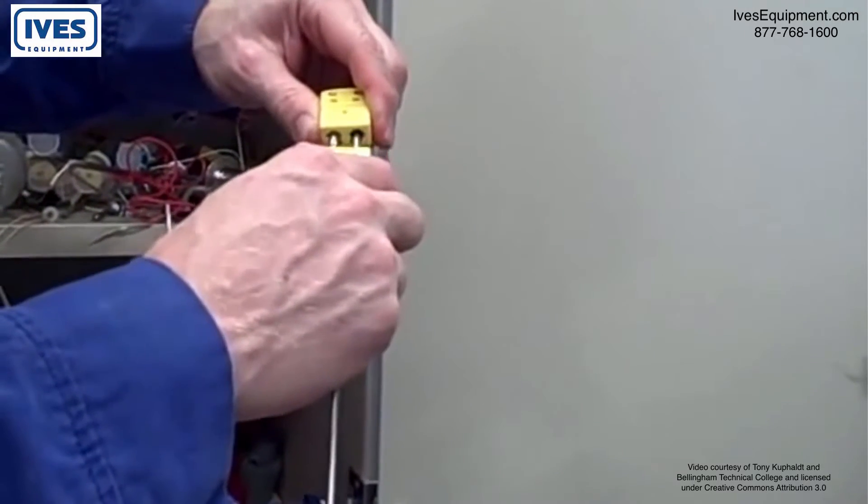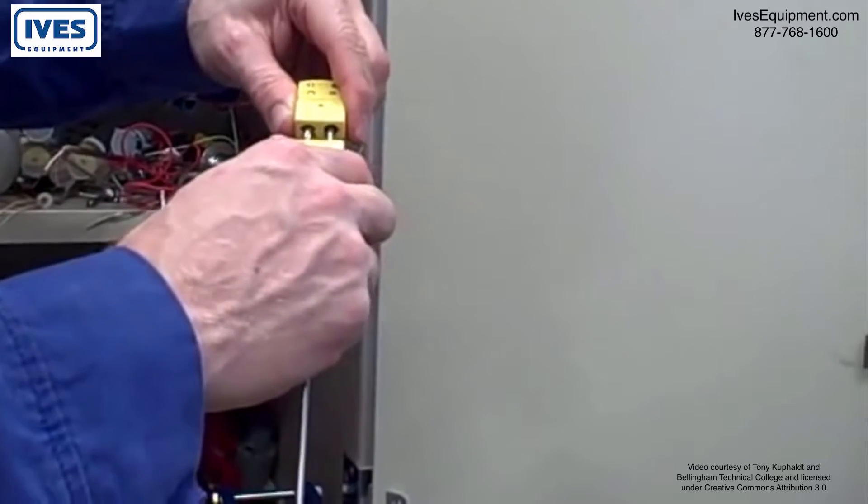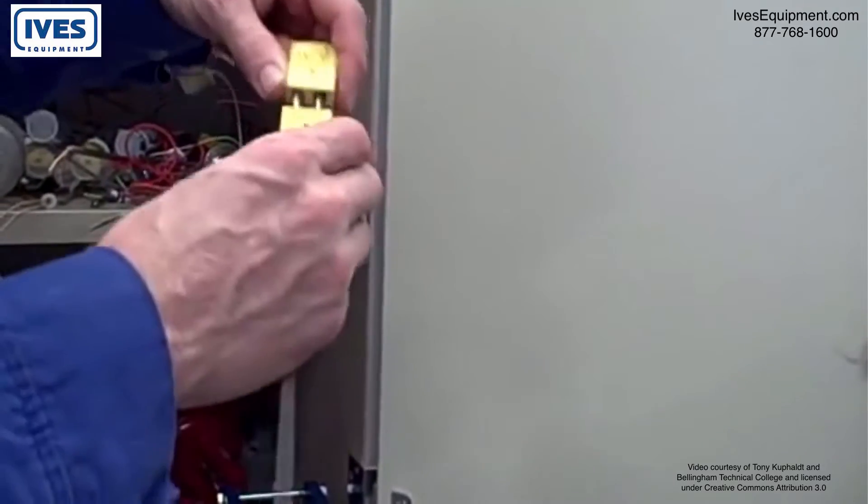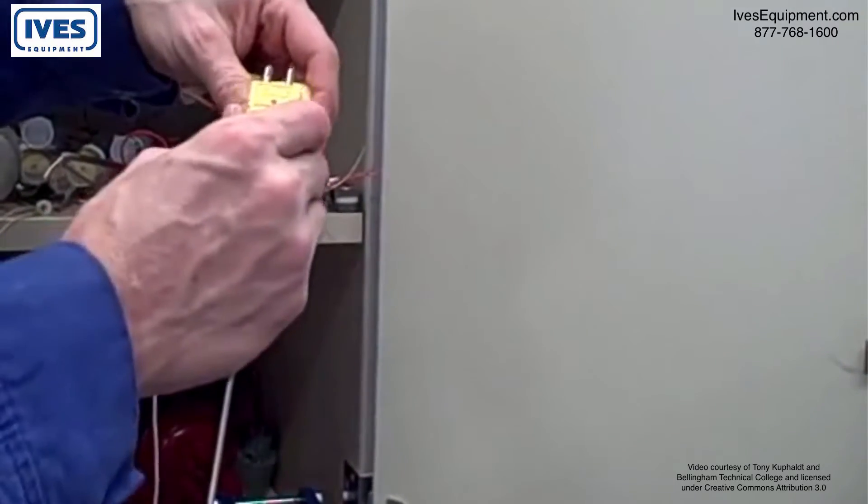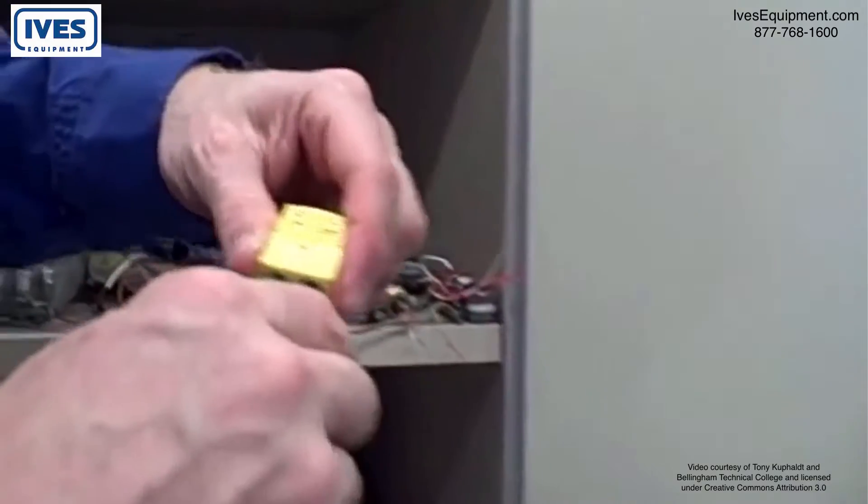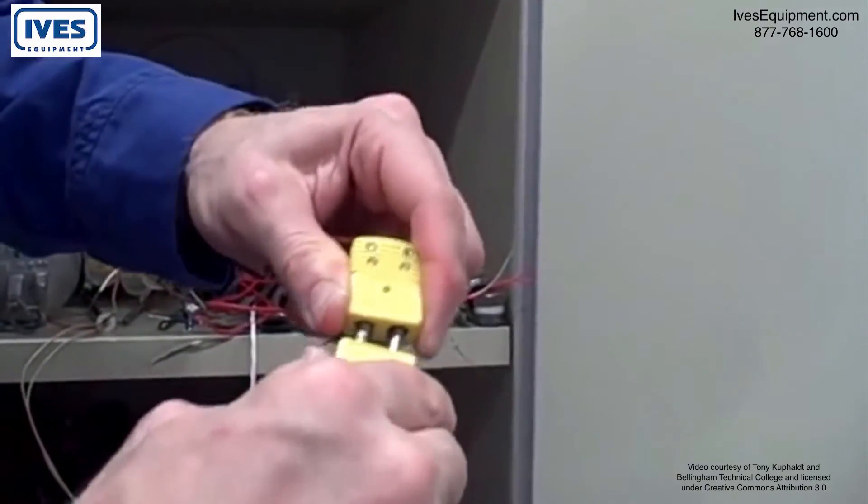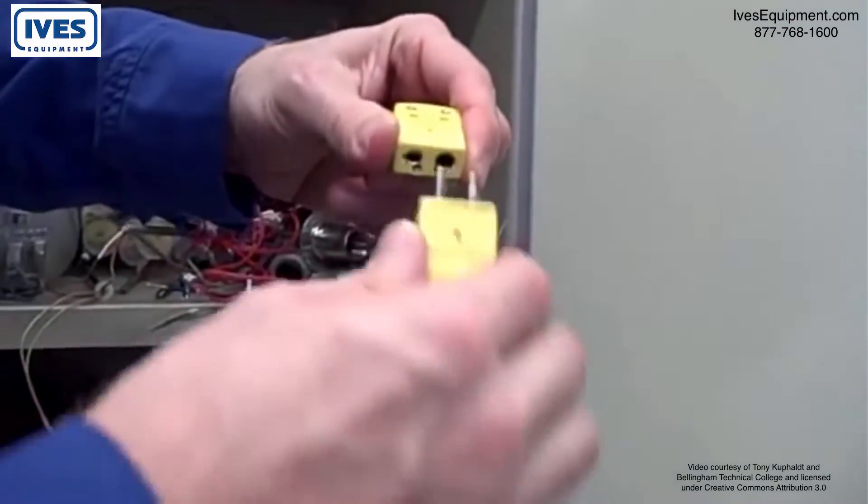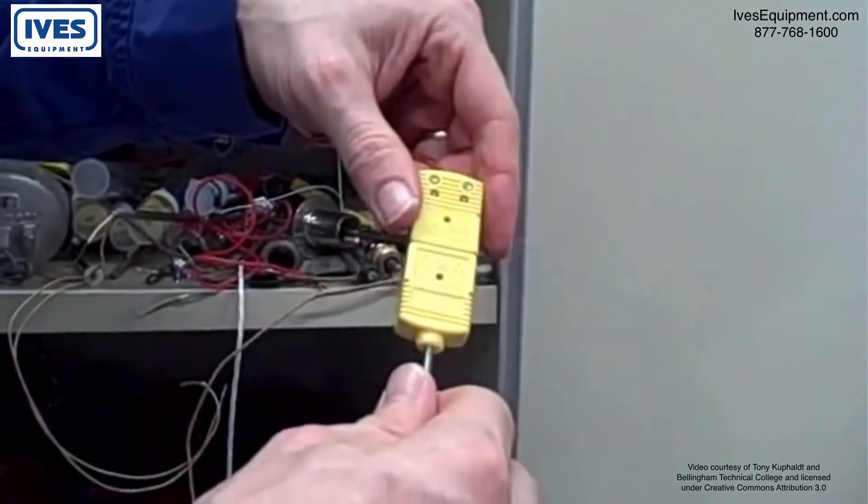However, never underestimate some people's ability to force connectors where they shouldn't go. I've seen thermocouple connectors shoved backwards like this. You really got to wonder about the person, but they put a lot of force in here and they actually managed to get it in. It's supposed to go in like this, a polarized plug.